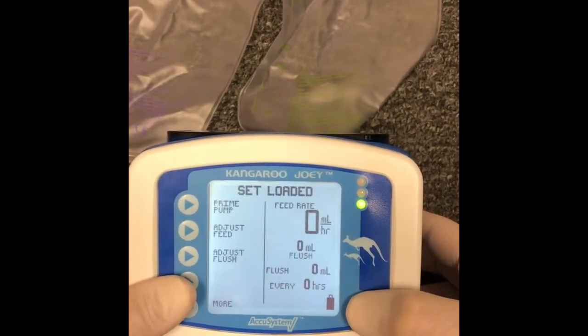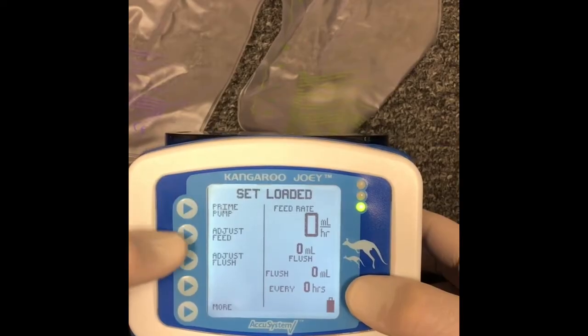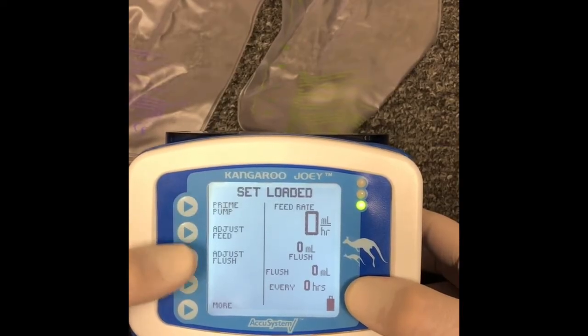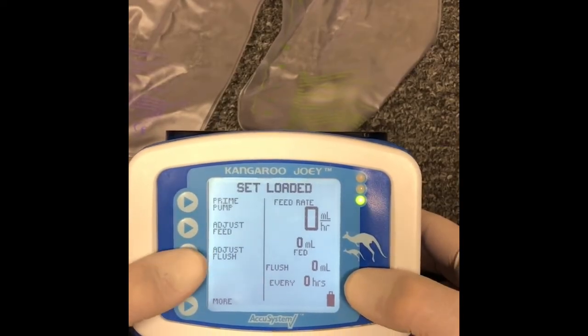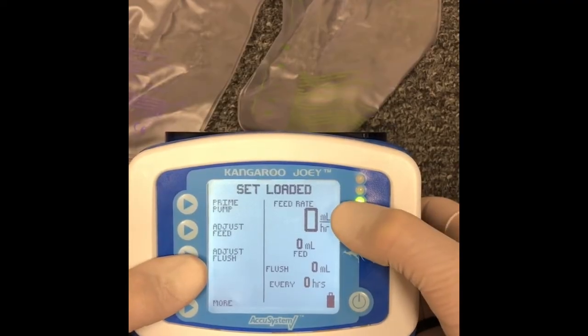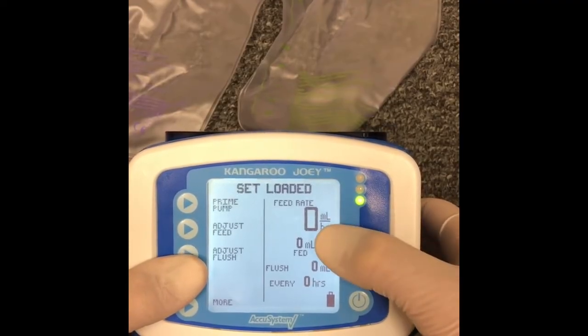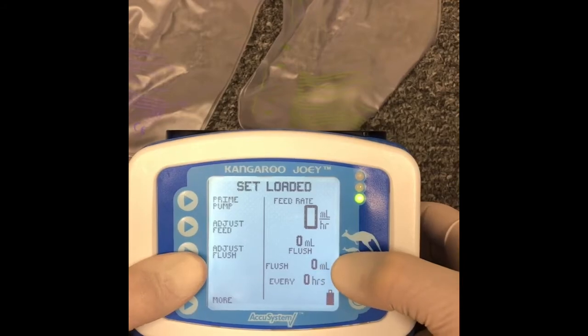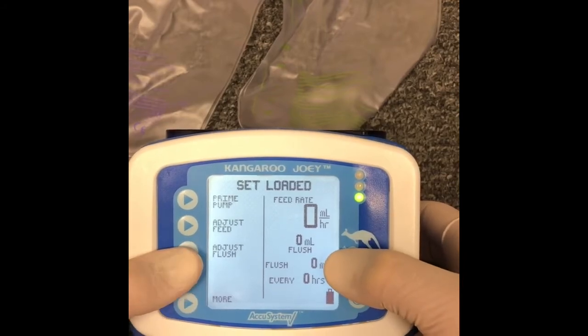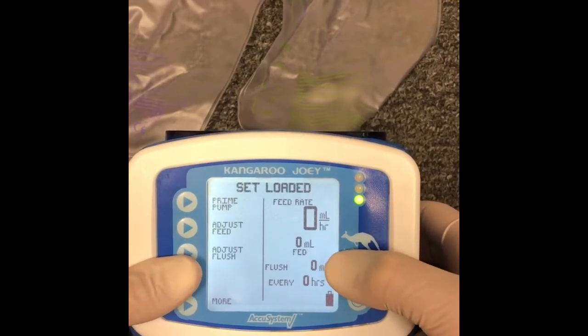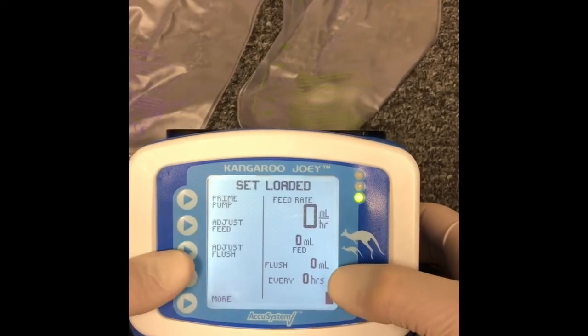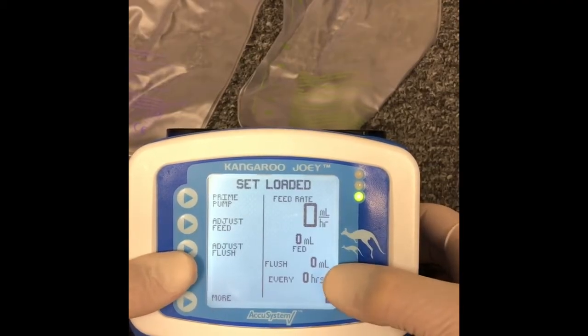So I'm doing clear settings, and we can see right here it has a little bit different options. It has prime pump, adjust feed, and adjust flush. Flush is the new part. So on the right side here, we have a little bit different settings. Same milliliter per hour, same milliliter fed, but we have flushing. So we have flushing this much. Right now it's set to 0. We can set that to whatever we want, 100. And we can flush every so often. So we can set how many hours. Every 6 hours do a flushing.